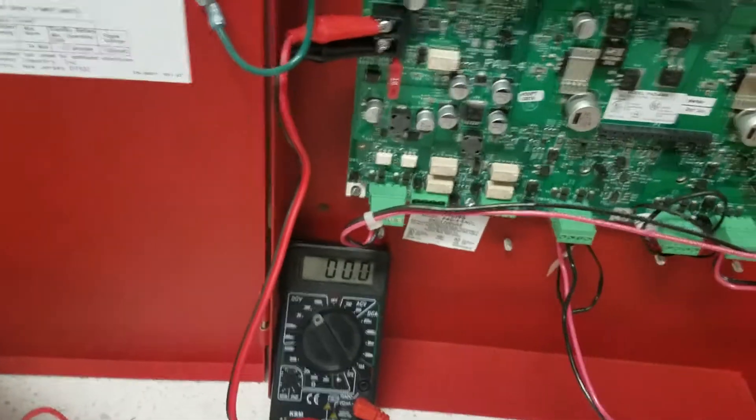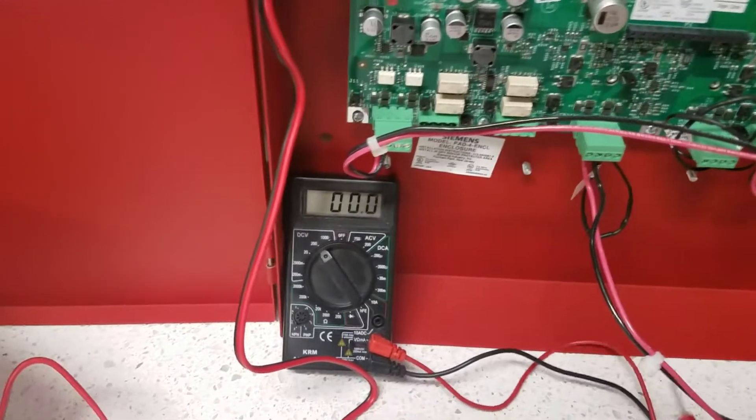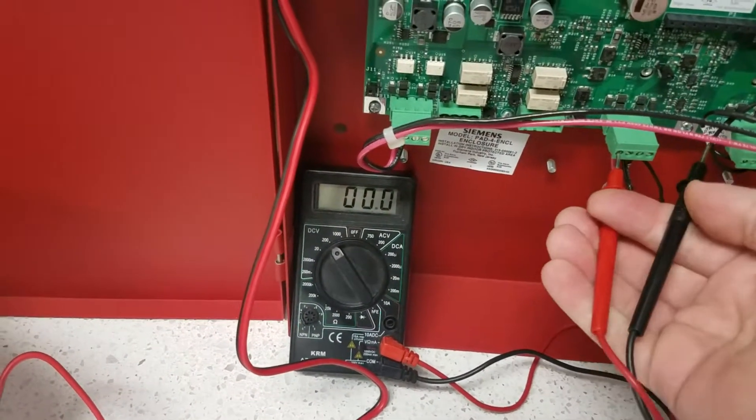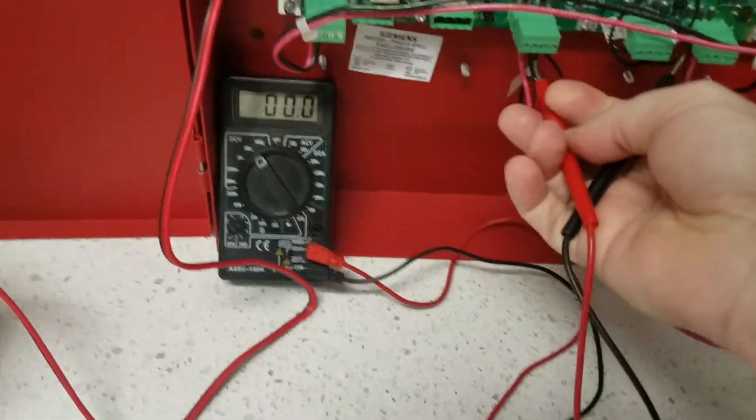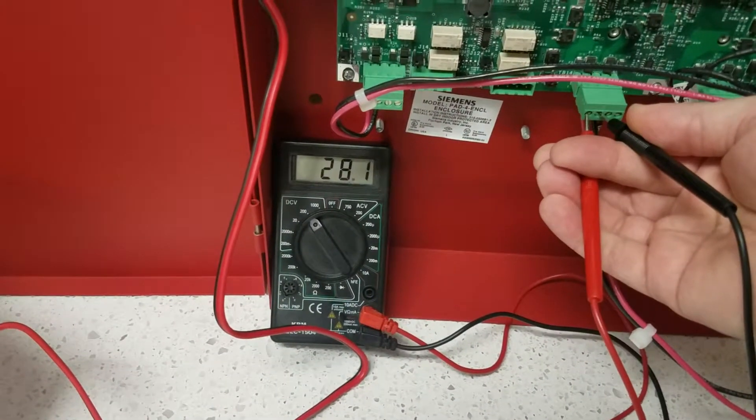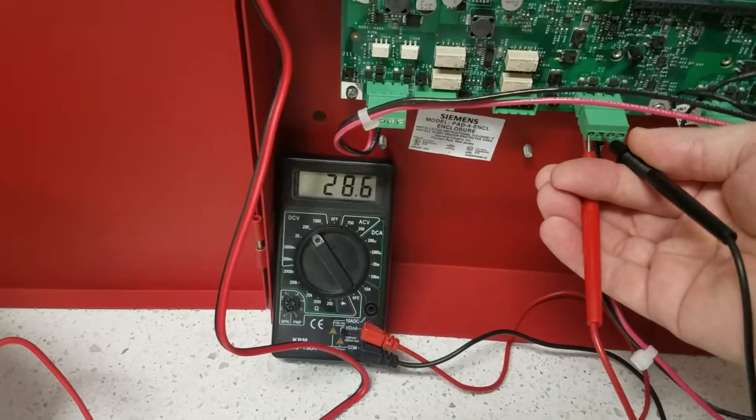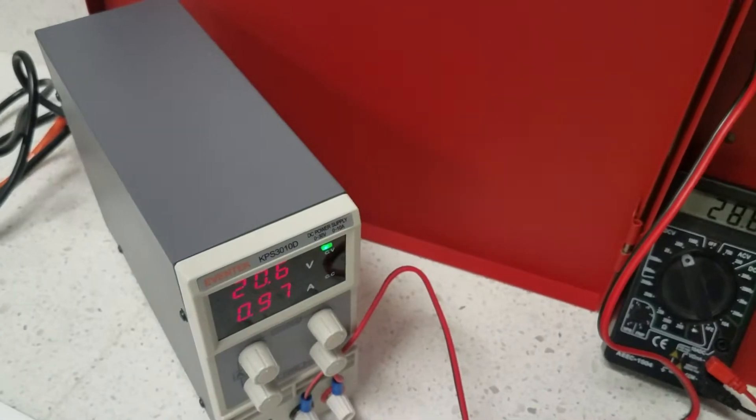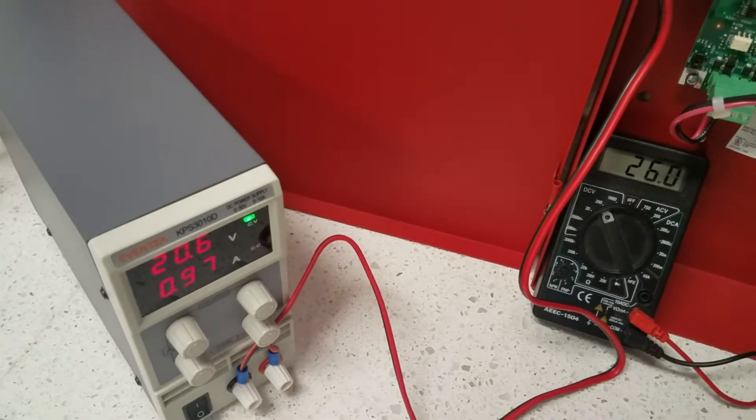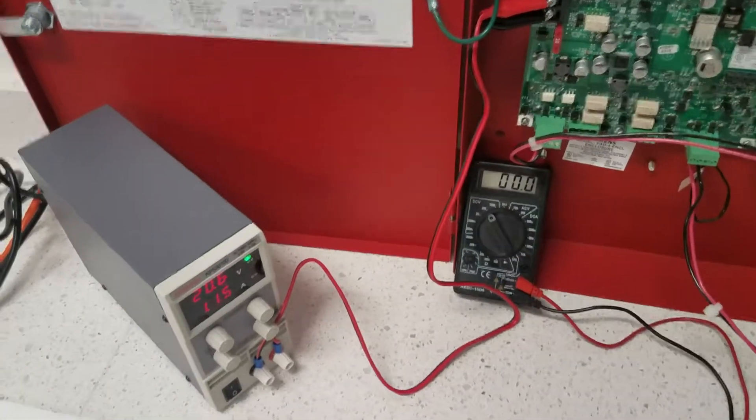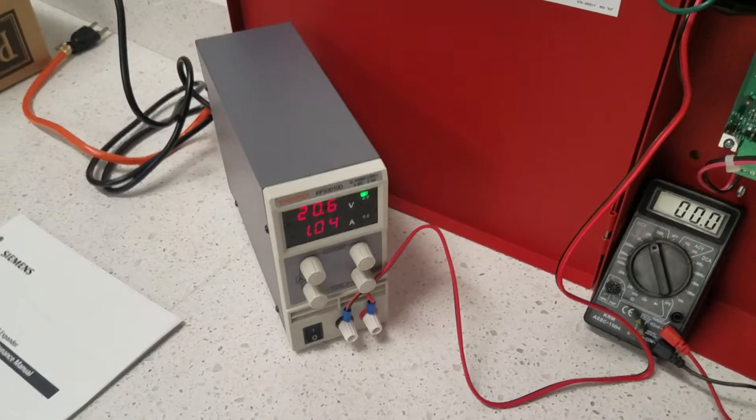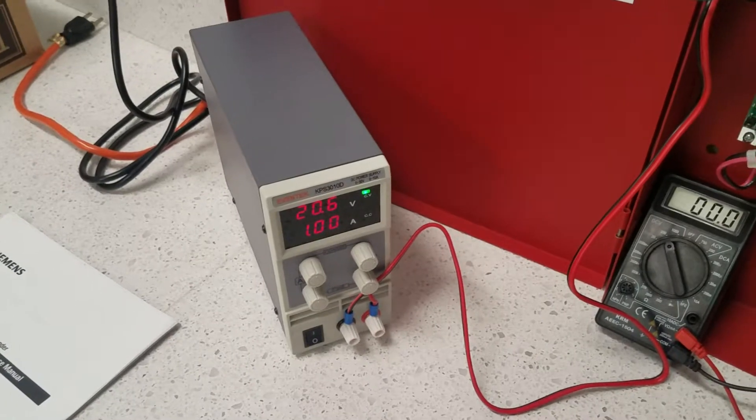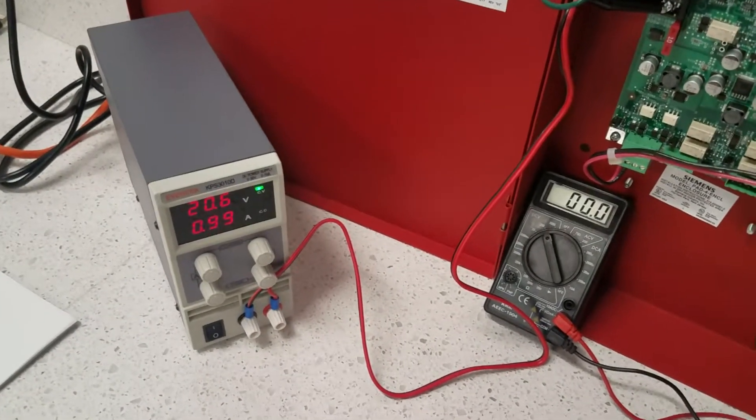Now, the question is, is there enough voltage to the notification appliance circuits? So with that, we're going to look at the voltage that is coming off of the terminals for the notification appliance circuits. So with that, I'm still getting 28 volts. How does that happen when you're only giving 20.4 volts from the batteries or these simulated batteries? That's where the power boost circuit comes in. It takes extra current to activate the power boost circuit, pulls from the batteries, and it ups the voltage to ensure that it has a full 24 volts out.